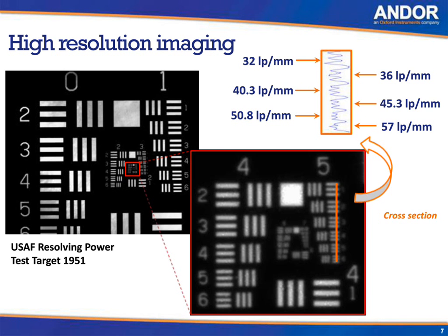So all this is about creating an efficient transfer mechanism for the light that is being generated in the scintillator. We're trying to match the efficiency and spatial resolution of the camera with the high quality scintillators that are being supplied by Crytur. So we don't want to effectively be limiting the efficiency and resolution of the system. That's fairly straightforward.